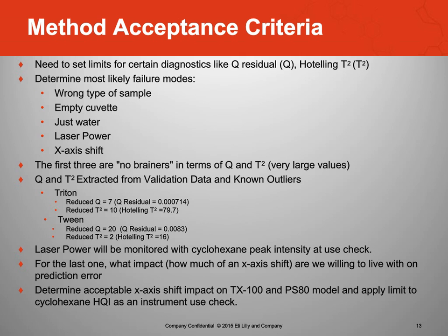From the data that we've generated to date, we knew that we could handle an acceptance criteria with a reduced Q of about 7 and a reduced T squared of 10. And that's for Triton, and for Tween it'd be 20 and 2 respectively. So those were the target values. Anything greater than those we'd consider to be outliers, and we knew that because we looked at the data we generated so far and said, hey, all this data is good. And then we generated some data with, for example, the polyethylene, and the polyethylene stood out as an outlier, so we drew the line between what we knew to be good data and bad data and picked those limits.